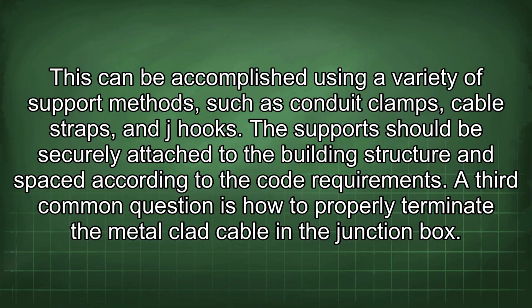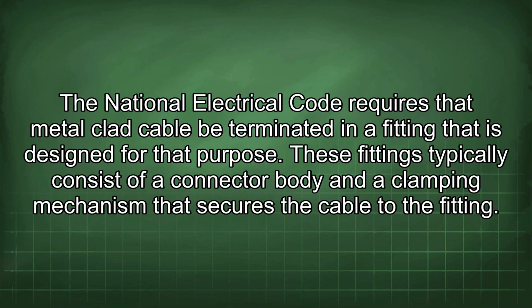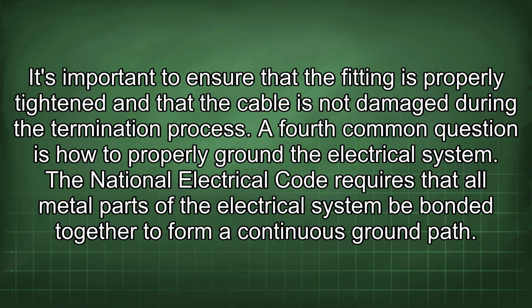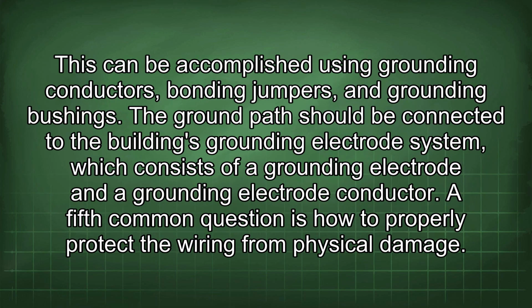A third common question is how to properly terminate the metal-clad cable in the junction box. The National Electrical Code requires that metal-clad cable be terminated in a fitting that is designed for that purpose. These fittings typically consist of a connector body and a clamping mechanism that secures the cable to the fitting. It's important to ensure that the fitting is properly tightened and that the cable is not damaged during the termination process. A fourth common question is how to properly ground the electrical system. The National Electrical Code requires that all metal parts of the electrical system be bonded together to form a continuous ground path. This can be accomplished using grounding conductors, bonding jumpers, and grounding bushings.